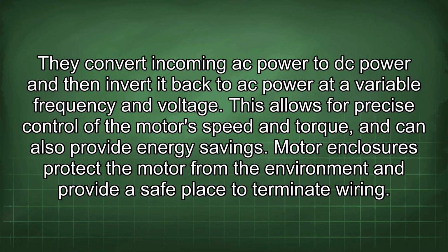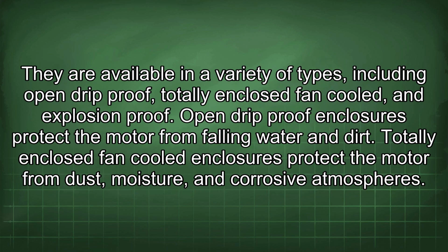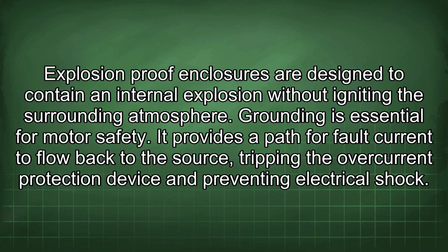Motor enclosures protect the motor from the environment and provide a safe place to terminate wiring. They are available in a variety of types, including open drip-proof, totally enclosed fan-cooled, and explosion-proof. Open drip-proof enclosures protect the motor from falling water and dirt. Totally enclosed fan-cooled enclosures protect the motor from dust, moisture, and corrosive atmospheres. Explosion-proof enclosures are designed to contain an internal explosion without igniting the surrounding atmosphere.